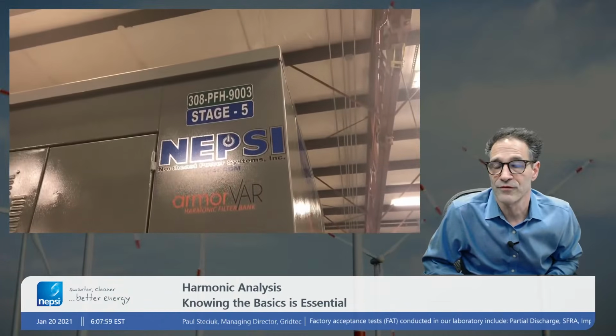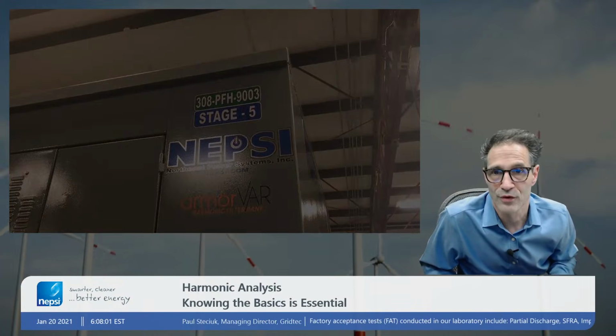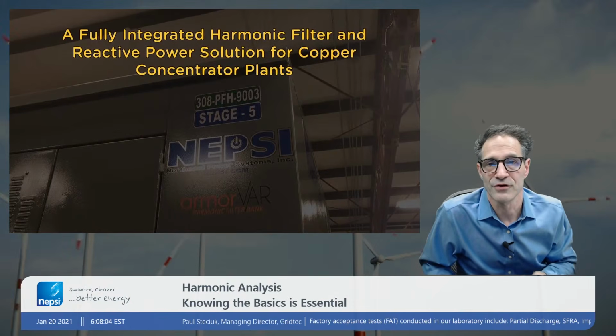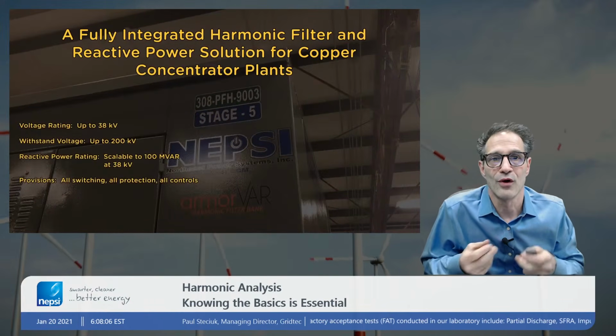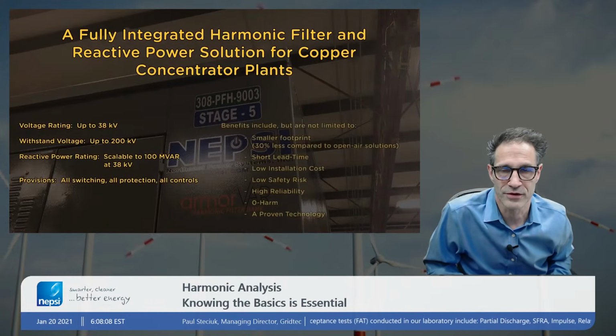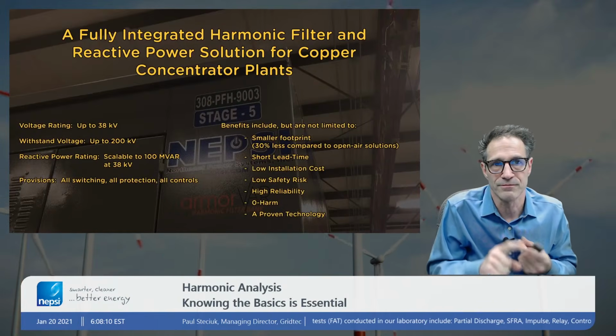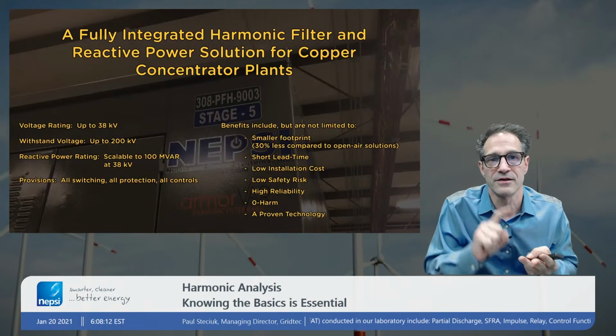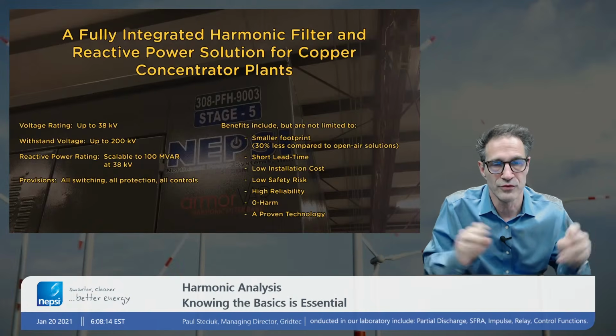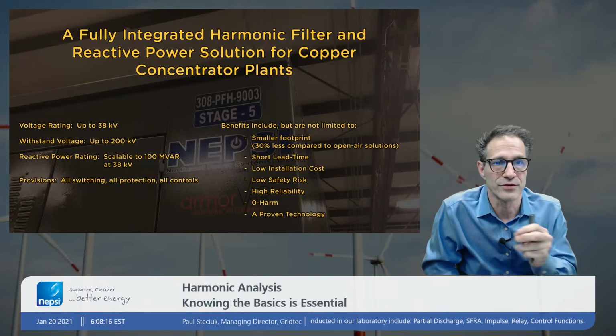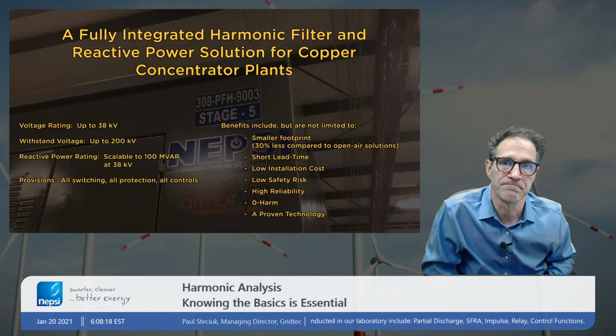So these systems come fully assembled, ready for interconnection. All switching, protection, and control is built within, and they're all tested at NEPSI before they leave the factory. Impulse tested, partial discharge tested, SFRA tested to confirm tuning points and the characteristic curves of that harmonic filter.